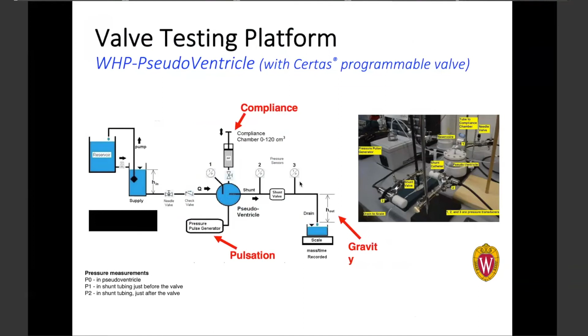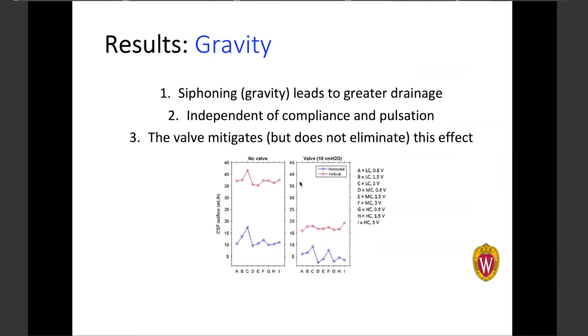And the Certas valve, we set it at a certain pressure. And what we found is that siphoning indeed leads to greater drainage than expected. And that's independent of compliance and pulsations. And then when you add a valve to the system, it decreases that siphoning, but it doesn't take it away.